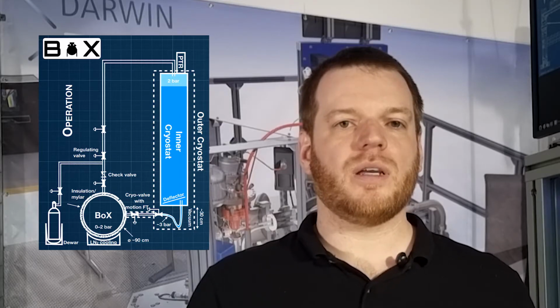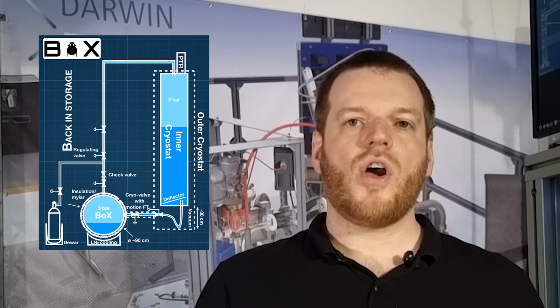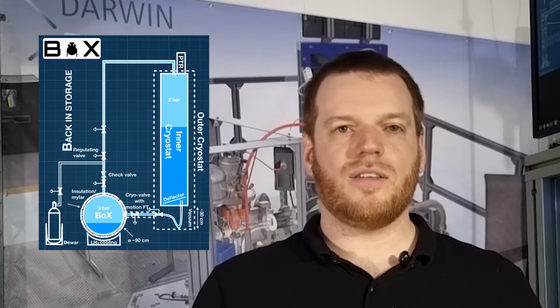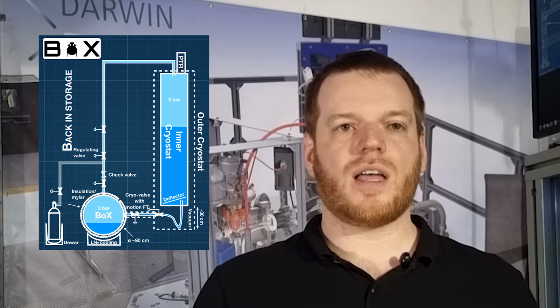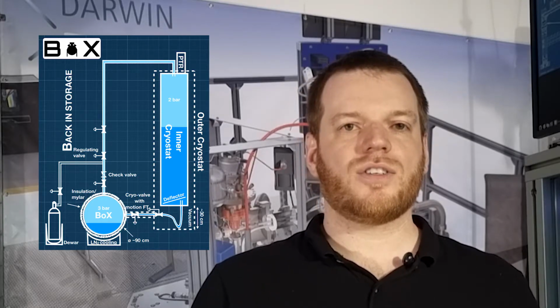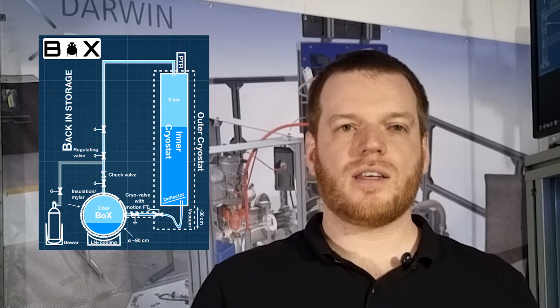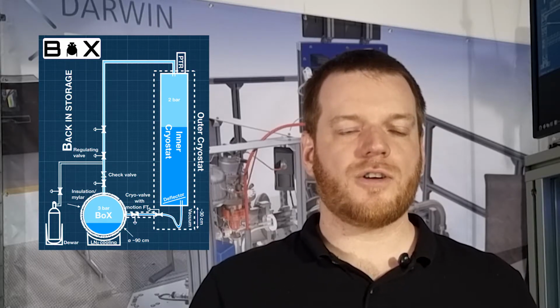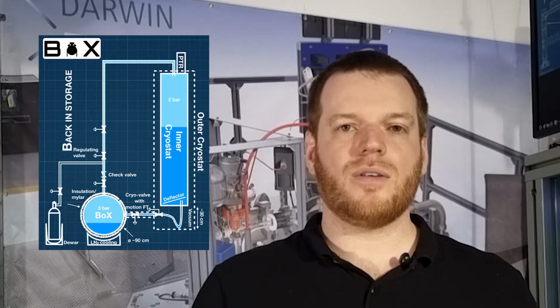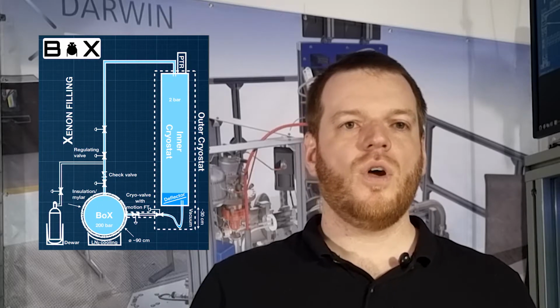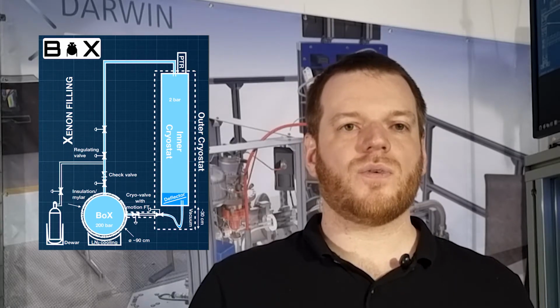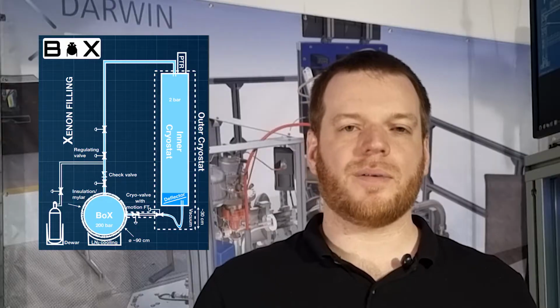The procedure is simple. BOX is pre-cooled with a copper cooling block, cooled with liquid nitrogen. When the pressure in BOX is about the same as in the cryostat, a cryogenic valve is open, allowing the liquid xenon to flow from the cryostat to the pressure vessel. The gas section of BOX is open to the gas section of the cryostat, equalizing the pressures, allowing the system to self-regulate the liquid transfer. When the liquid transfer is finished, the remaining gas from the cryostat can be transferred to the gas storage system by cryopumping.